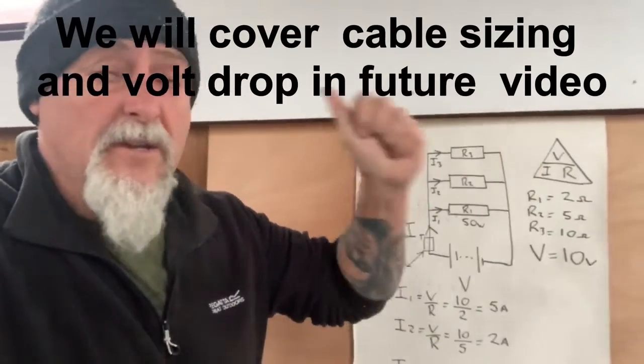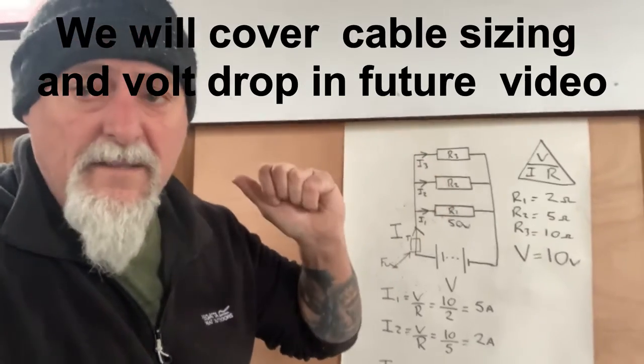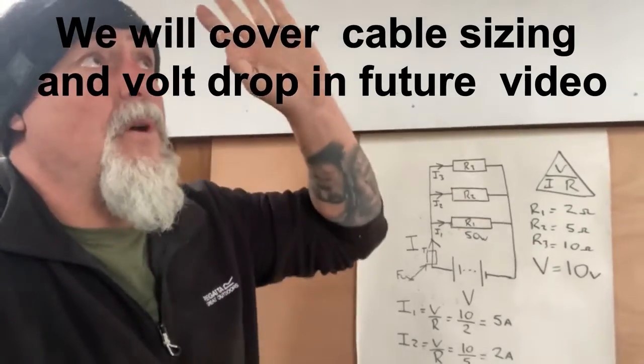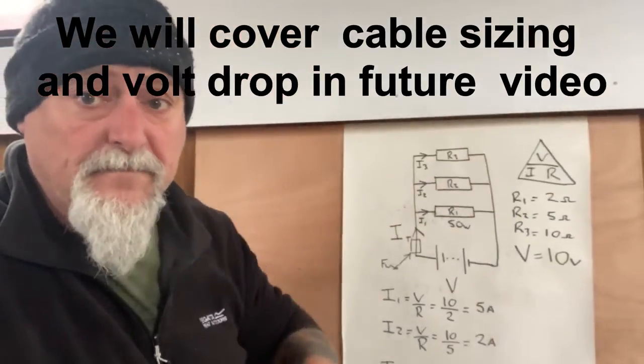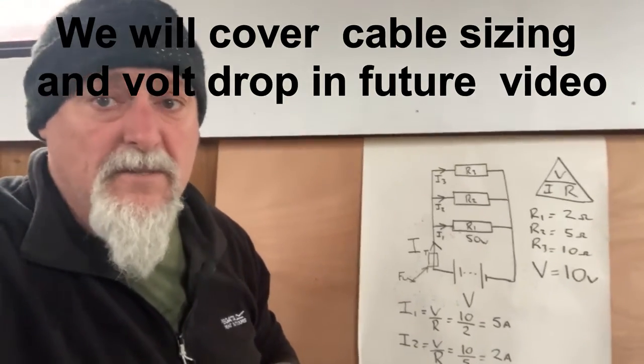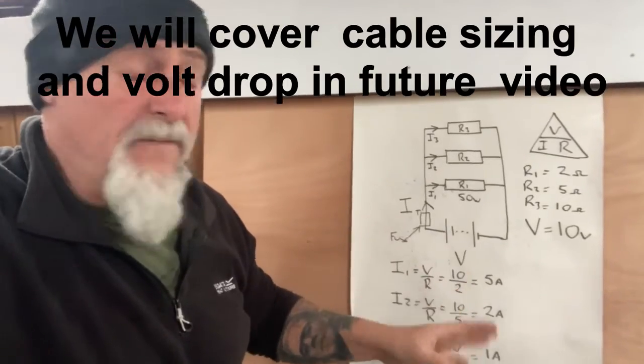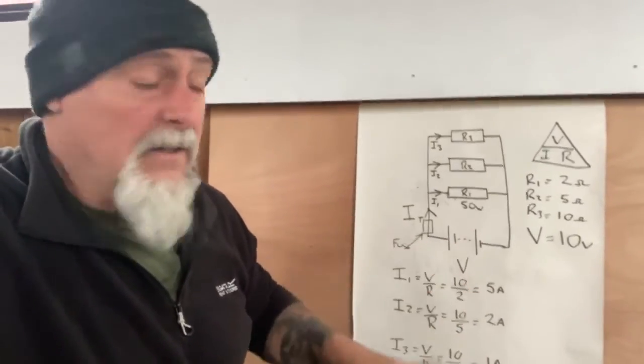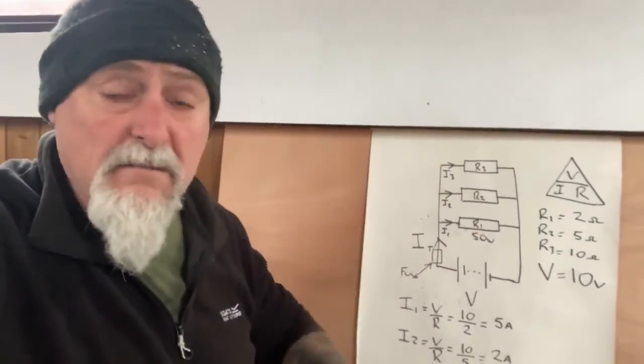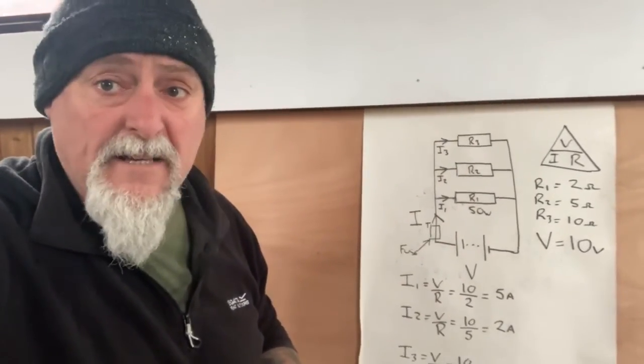But all pumps will tell you what current they take at the voltage. So you can work it out, you can work out the cable, you can work out the fuse sizes. And if you were wiring an array of lights, you could work out the cable sizes and fuse sizes for those as well. This is super important when we're talking about electrics on a boat. In fact, anywhere, all this stuff comes into play. If you can get this going around your head, and it works for you, then fantastic, I've done my job.